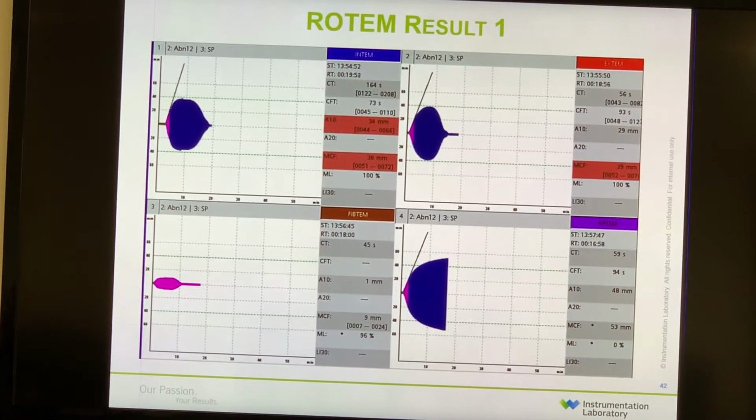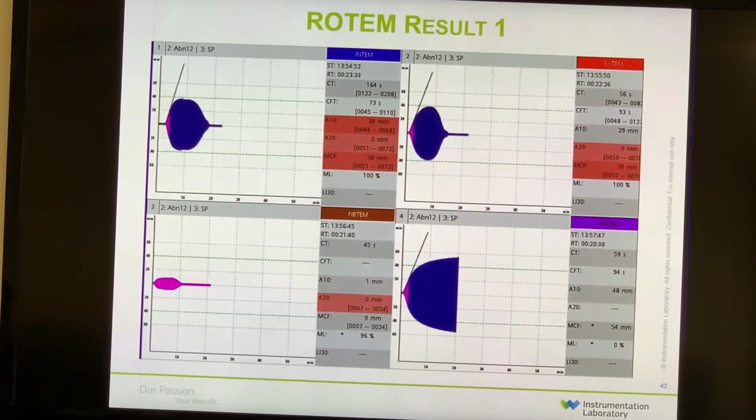What if there's 2 or 3 patients that are needing this? Then somebody has to decide, they'll have to do a little triaging with the samples, a little communication back and forth with the providers to find out. Can you run 2 different patients on 1 machine? The device has no safeguards in place for running 2 patients. If you do so, it's at your own risk, because we don't run it, the lab's going to run it, we just want to tell them what to do, so we can't tell them to run 2 patients.